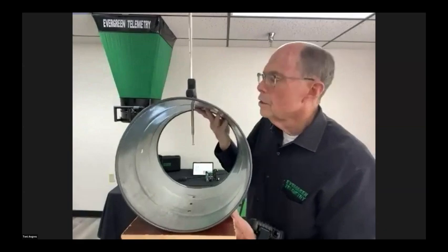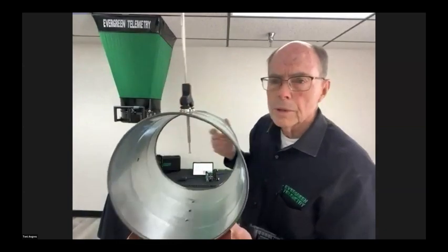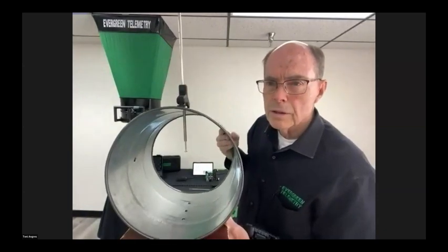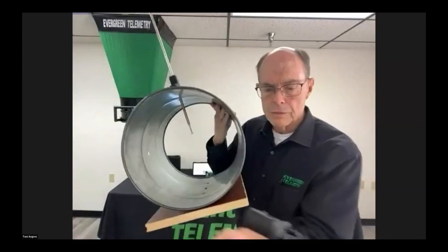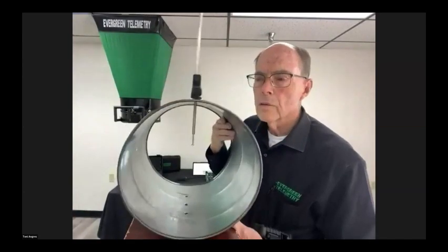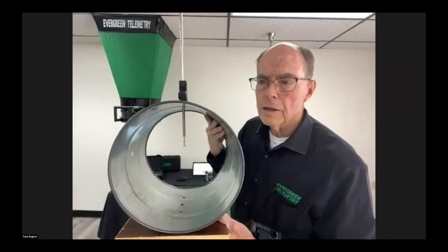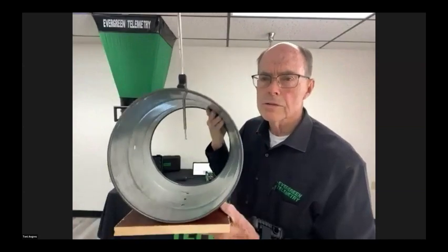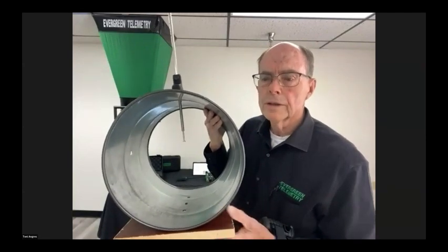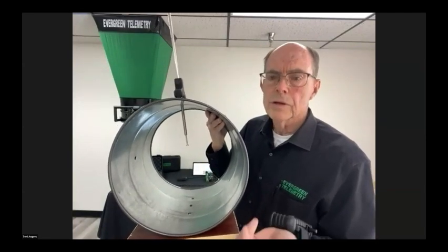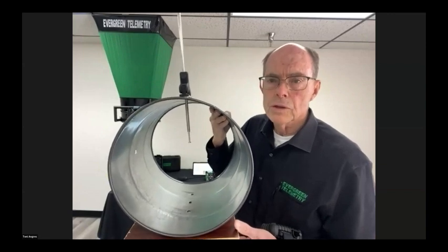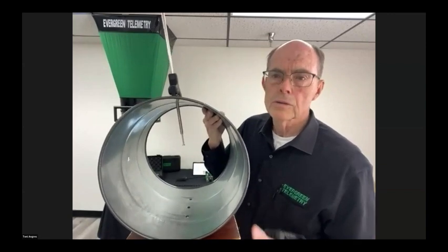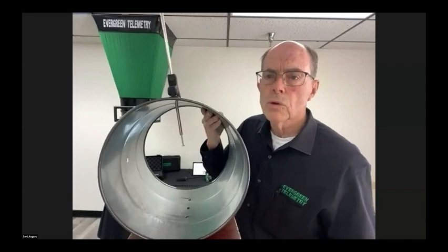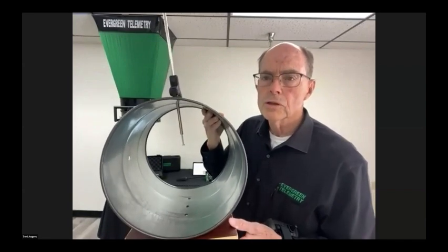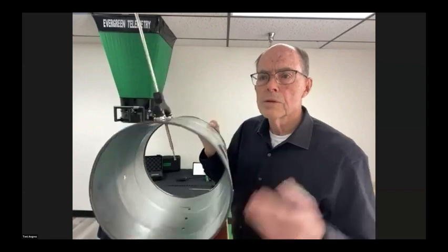I'll hold the duct up a little closer so you can see. Basically, set the probe up to get a center line of velocity. The result comes to your wrist on the wrist reporter. Now when you go over to the damper or the fan to make a change, let's say you want to reduce the CFM by 20%, what you can do as a reference is check the velocity of the center line. When that goes down by 20%, you're achieving roughly a 20% reduction in CFM, so you're just saving the back and forth.